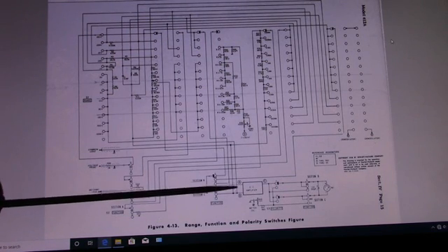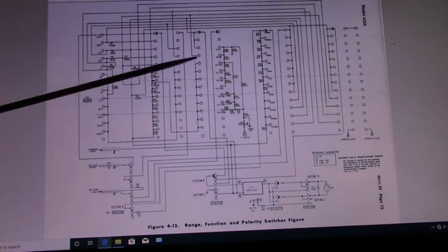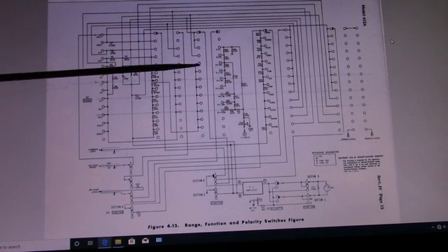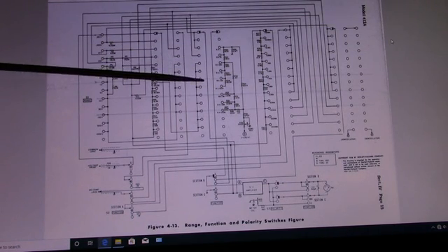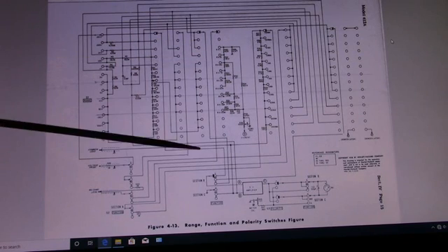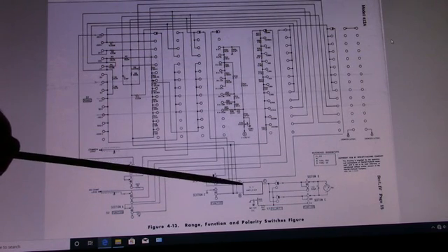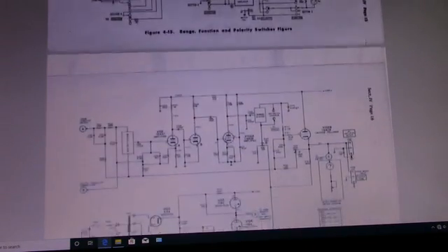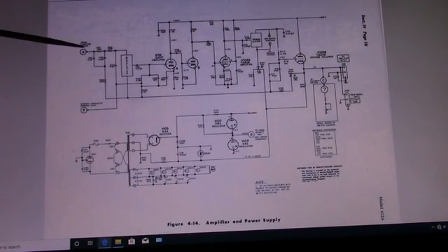So the input signal is processed so it can be fed into the amplifier assembly. If you look down here, A and B, this is where the attenuator network, and this is on a big drum wafer switch assembly that you can pick the different scales. But A and B are the two points where it's connected into the amplifier. And that's the next diagram here. Here's point A and B from the attenuator assembly, and the signal goes through a filter and into the modulator, and here's where the signal is chopped into a square wave and applied to the amplifier here.